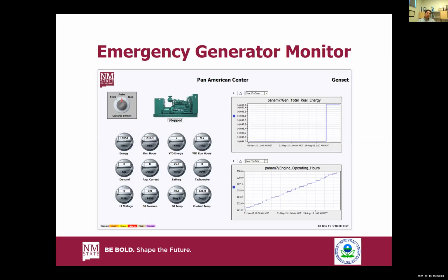This is important from an EPA perspective, because as an institution using this equipment, we're bound by air permits that allow us to operate certain equipment in a certain manner. Emergency generators are pieces of equipment that sometimes slip through the cracks for building owners who aren't aware they have a limitation on how many hours they can run, since they're not considered utility production generators and are typically less efficient. They emit more pollutants. If you exceed a certain number of run hours based on your annual permit, you can actually be fined for that.